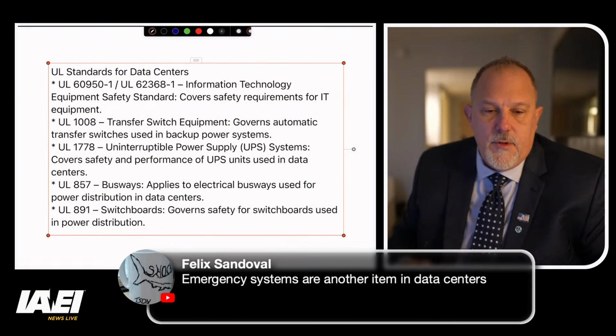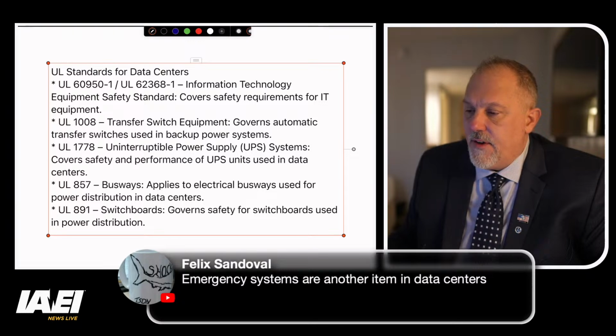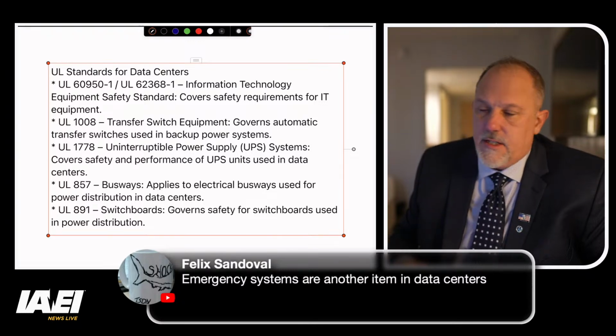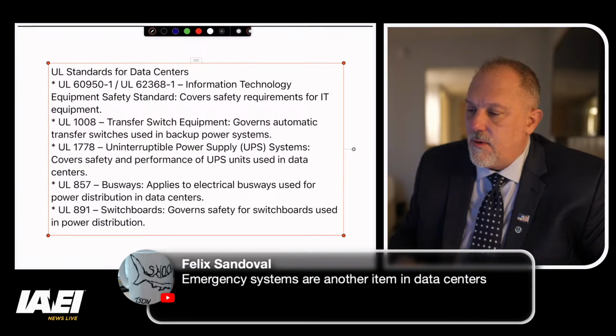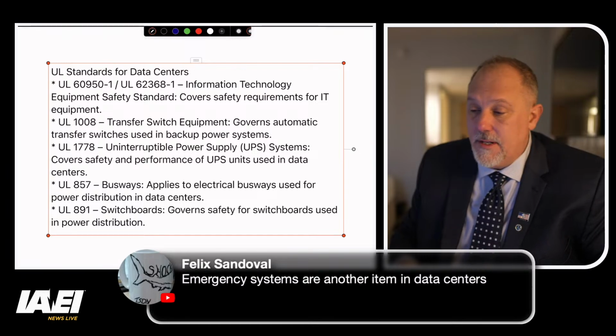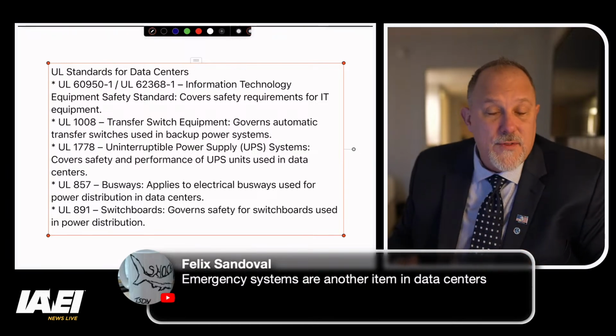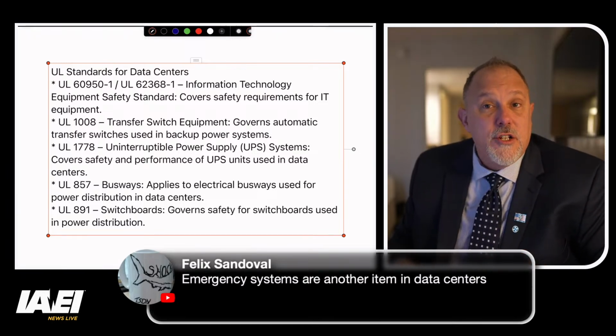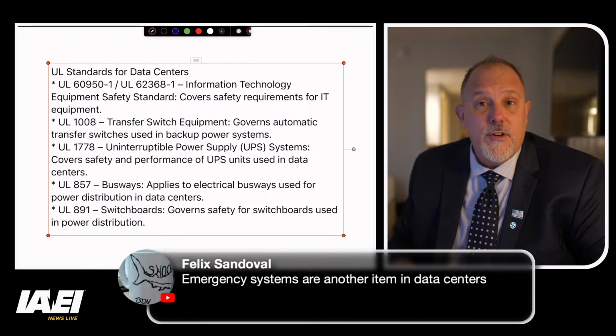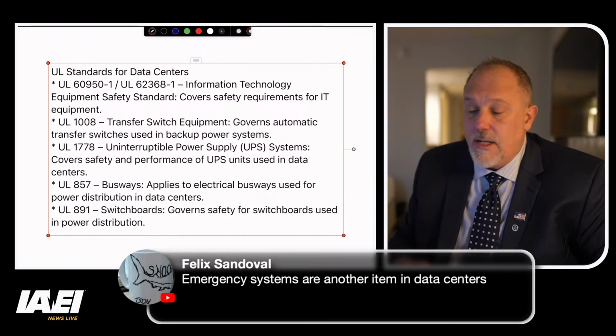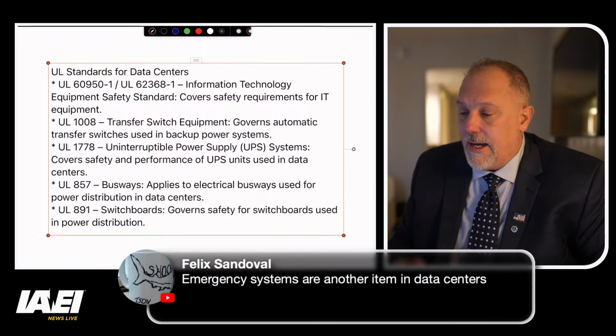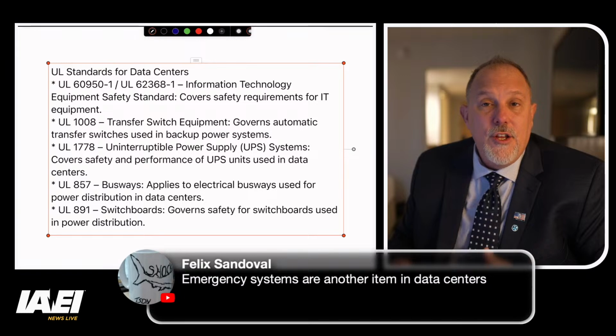All right, so here's some UL standards. We have UL 60950-1, 62368-1 for information technology equipment safety standard, covers safety requirements for IT equipment. You have 1008, that's your transfer switches - anything you're going to use in an Article 701, 708, or Article 700 application, if it's a transfer switch, you're going to need it as a UL 1008 application. 1778 for UPSs, don't you think?